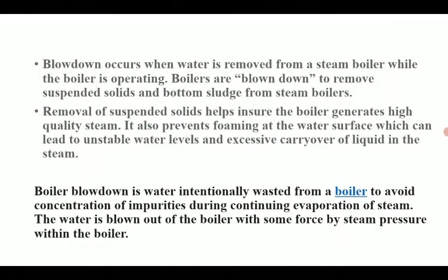Boiler blowdown occurs when water is removed from a steam boiler while the boiler is operating. Boilers are blown down to remove the suspended solids and bottom sludge from the steam boiler. That is discussed in the internal treatment. So if you have suspended sludge, you can remove it by boiler blowdown. So what is boiler blowdown? Boiler blowdown means the removal of waste water and waste particles which are suspended at the bottom of the boiler.